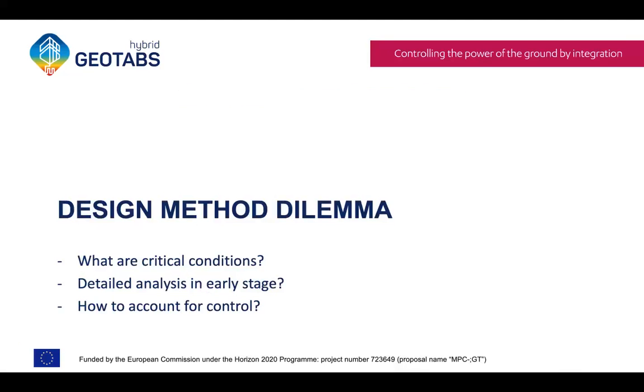So really, we try to answer three questions. First of all, what are critical conditions for design that are associated with this type of hybrid system? It's not self-evident that these are the same conditions as we traditionally take. Traditionally, we design for peak cooling and peak heating demand. However, because two systems need to interact, the most critical condition for each of the components is not necessarily the critical condition for the whole system together.